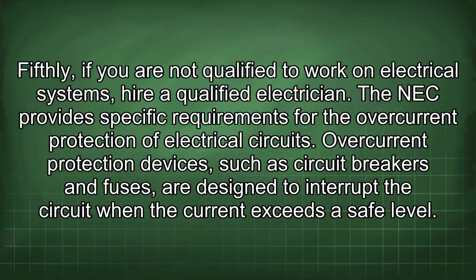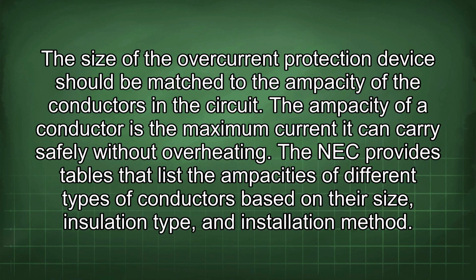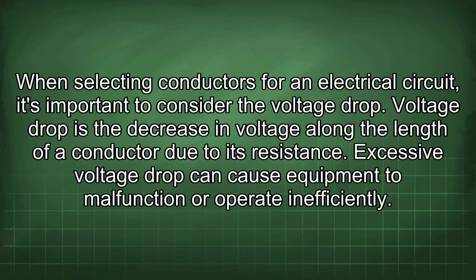The NEC provides specific requirements for the overcurrent protection of electrical circuits. Overcurrent protection devices, such as circuit breakers and fuses, are designed to interrupt the circuit when the current exceeds a safe level. The size of the overcurrent protection device should be matched to the ampacity of the conductors in the circuit. The ampacity of a conductor is the maximum current it can carry safely without overheating. The NEC provides tables that list the ampacities of different types of conductors based on their size, insulation type, and installation method.